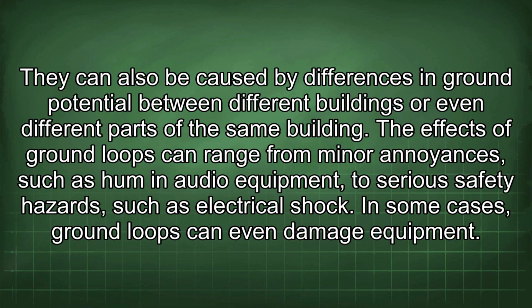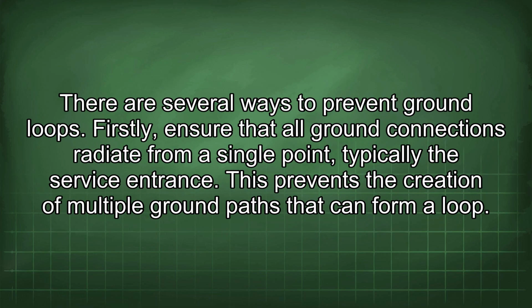They can also be caused by differences in ground potential between different buildings or even different parts of the same building. The effects of ground loops can range from minor annoyances, such as hum in audio equipment, to serious safety hazards, such as electrical shock. In some cases, ground loops can even damage equipment. There are several ways to prevent ground loops. Firstly, ensure that all ground connections radiate from a single point, typically the service entrance. This prevents the creation of multiple ground paths that can form a loop.